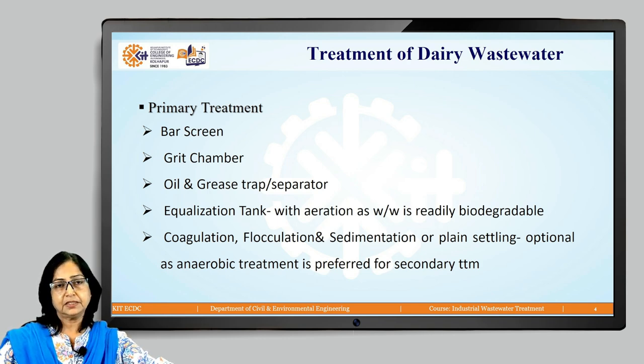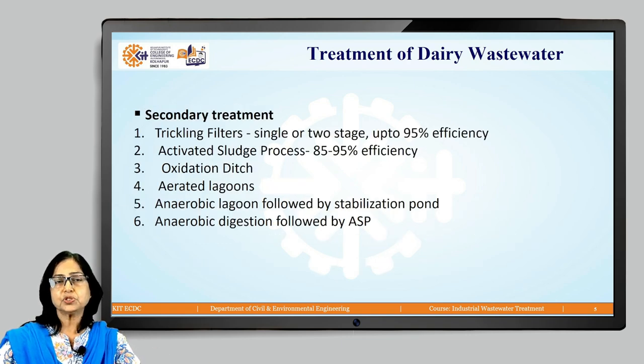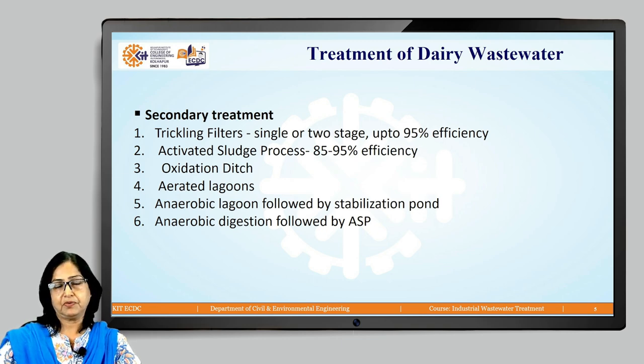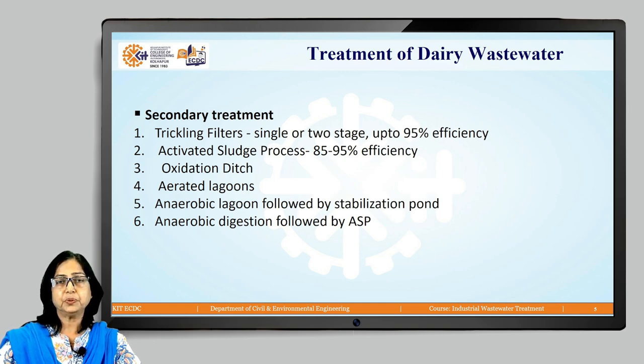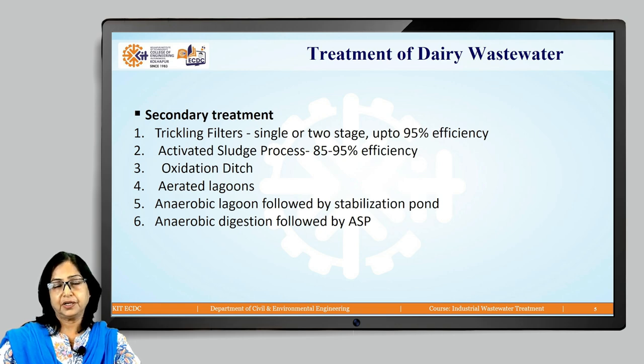Most biological treatment processes are suitable and can be employed efficiently for dairy wastewater treatment because the wastewater is readily biodegradable. A trickling filter — single stage or two stage — achieves up to 95% efficiency. The activated sludge process (ASP) is very popular, with efficiency in the range of 85–95%. An oxidation ditch, which is a cheaper alternative to ASP, is also popular, as are aerated lagoons.